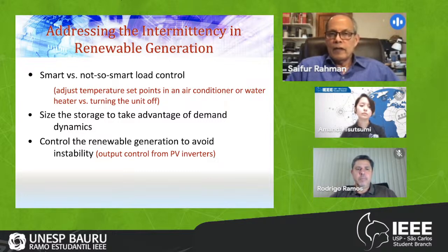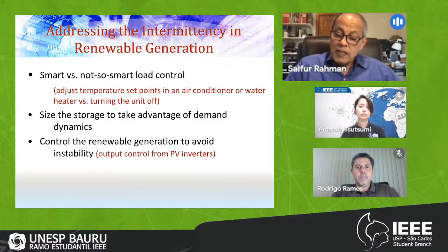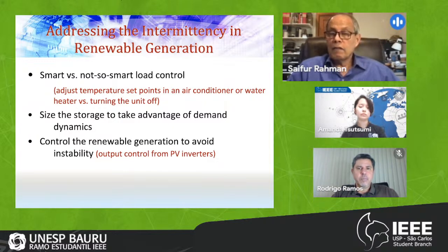Similarly with battery, yes, you can buy all the batteries in the world you want and keep full backup. You can do that, but that gets very expensive and space is an issue. If I can predict, for a short lead time, what my load is going to do, I can then play with that load variation when my rooftop solar fluctuation is causing problems. That's what I mean by sizing the storage to take advantage of demand dynamics. I'm not saying zero storage, storage is there, but not as much, because I can manage some of the fluctuations using demand control.